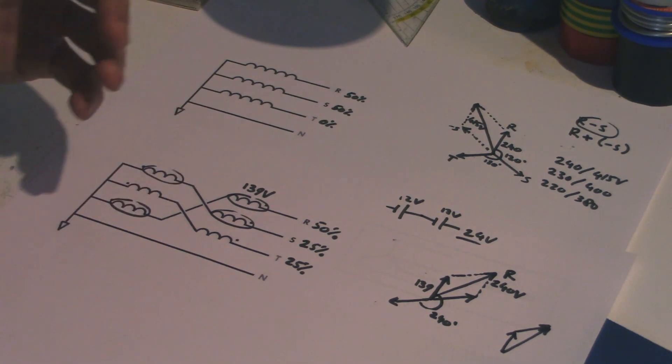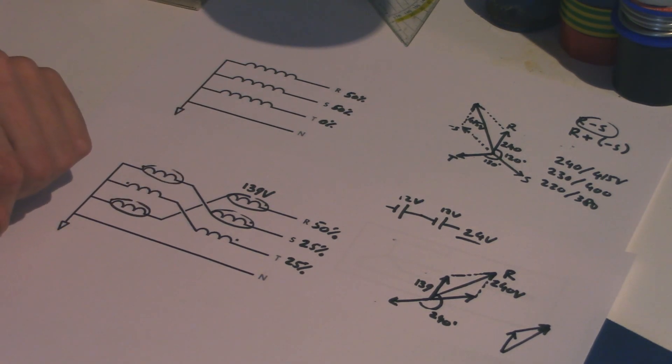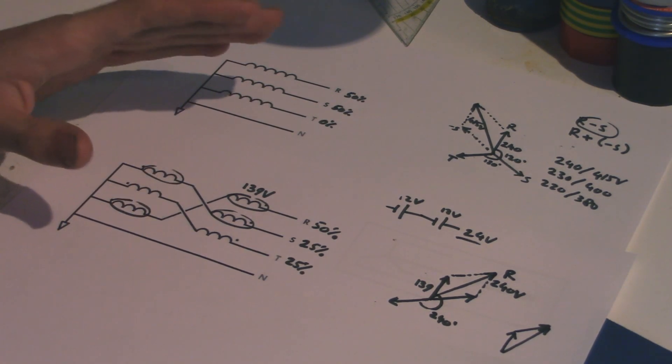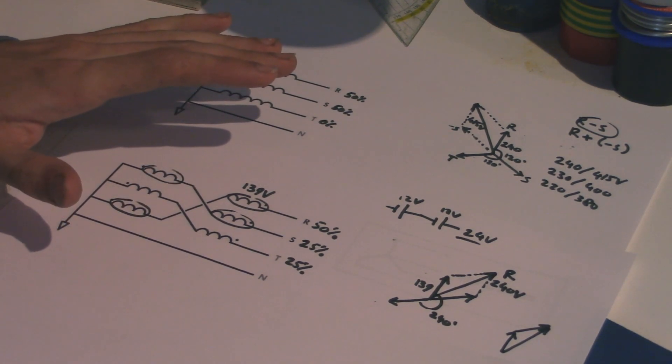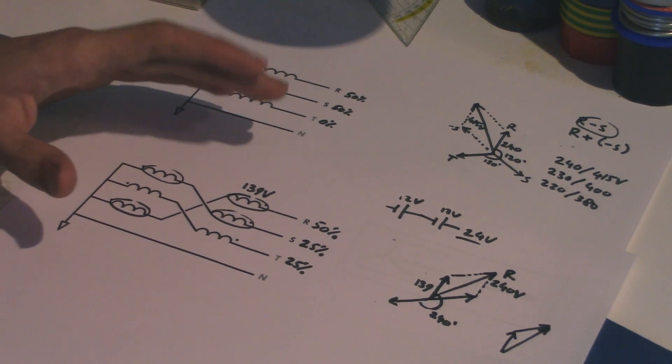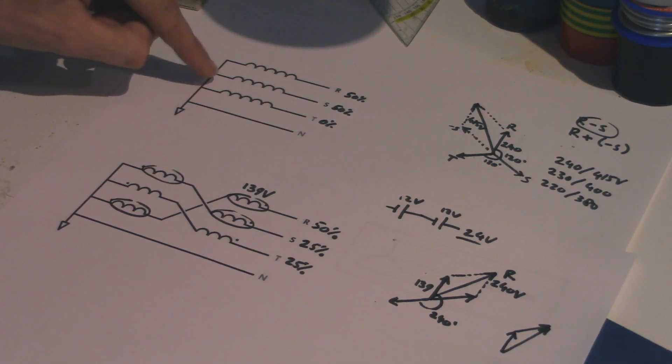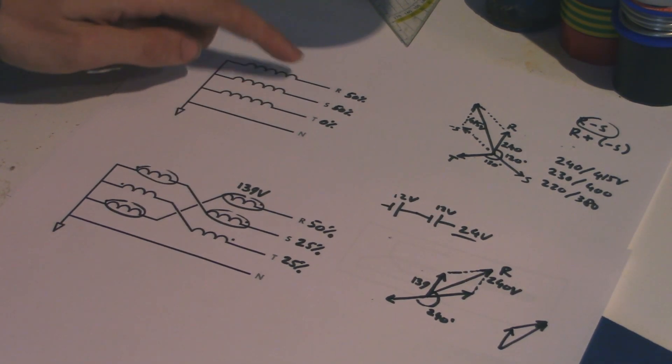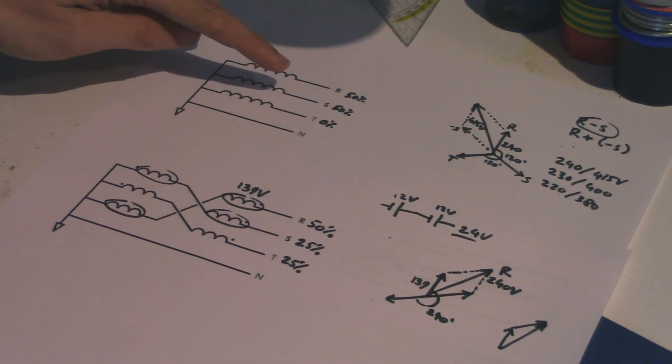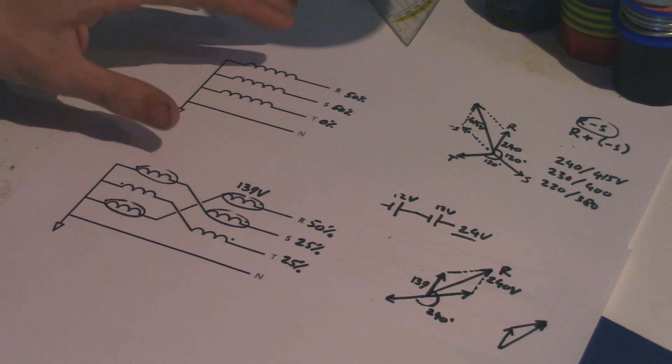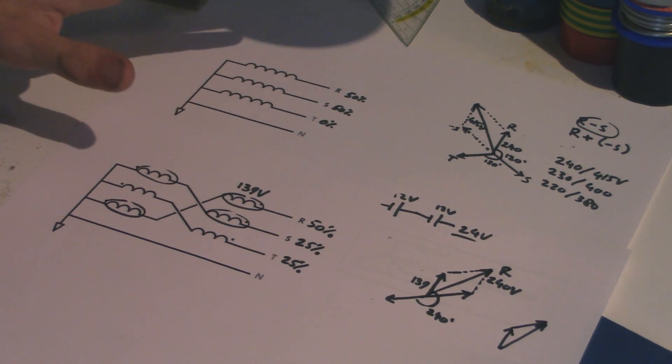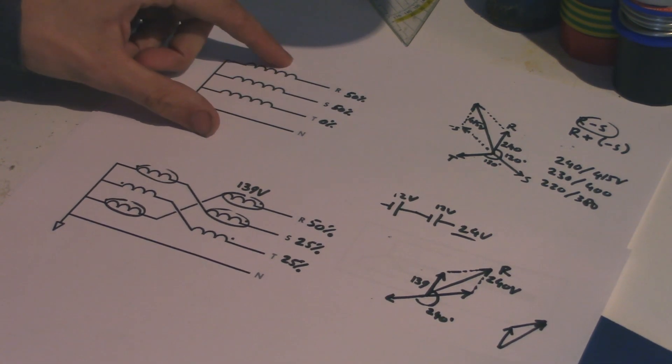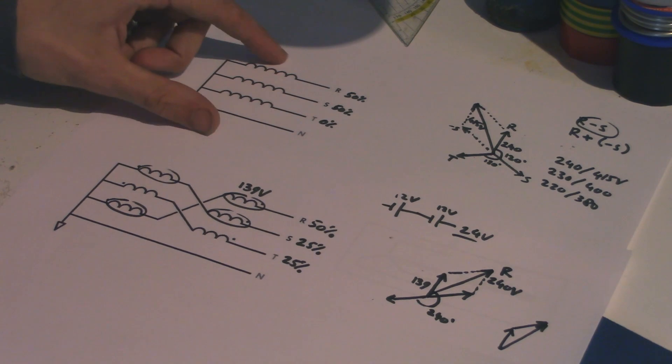It's when you have absolutely terrible balance between your phases, you can use this to spread out the load a bit better. Now, most of the time, the balance isn't quite that terrible. And in that case, it's better to use this, because this is a cheaper transformer to build. So if the balance is pretty acceptable, they tend to just use this, which is why this is a far more common type of transformer. So now hopefully you know a little bit more about three-phase transformers, and particularly about zigzag transformers, of course.